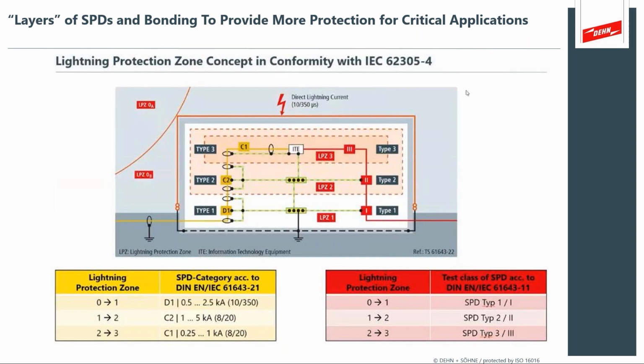As I mentioned, this particular topic can go on for quite a number of slides, just looking at all the variations and permutations. This might be a really good one to have a follow-up discussion on. Yes, I just want to mention that when we install surge protection devices into a power system, we have something that we call follow current and follow current limitation. Whenever we have a lightning impulse or surge current, we want the SPD to safely divert this to earth and then go back into a high impedance state, so we don't have a very large power system frequency follow current that goes through the SPD.